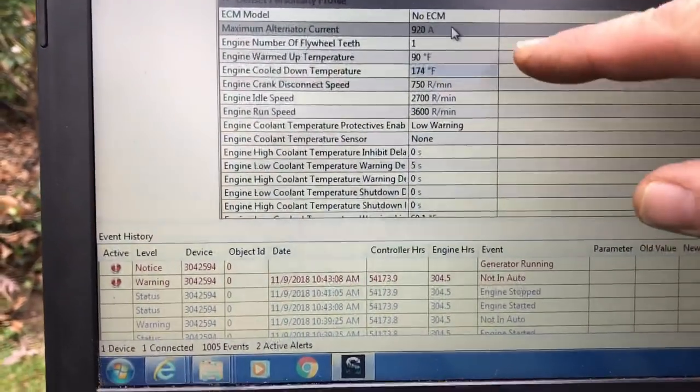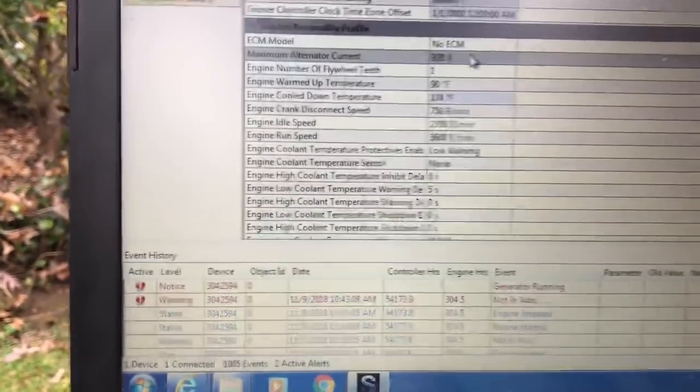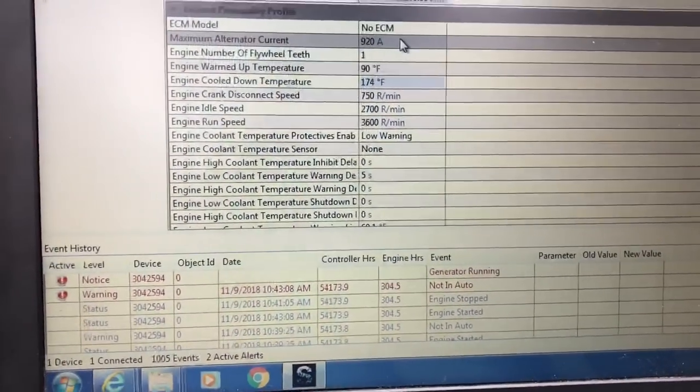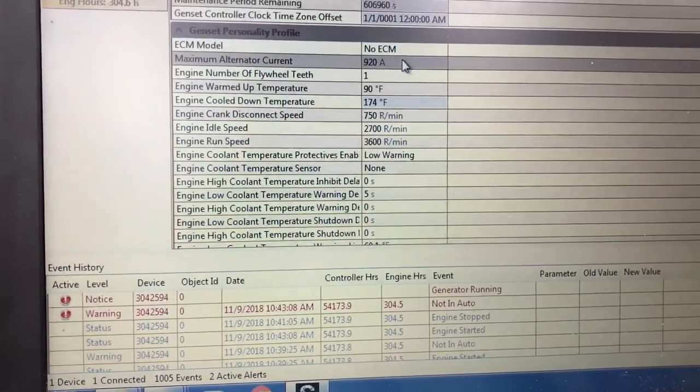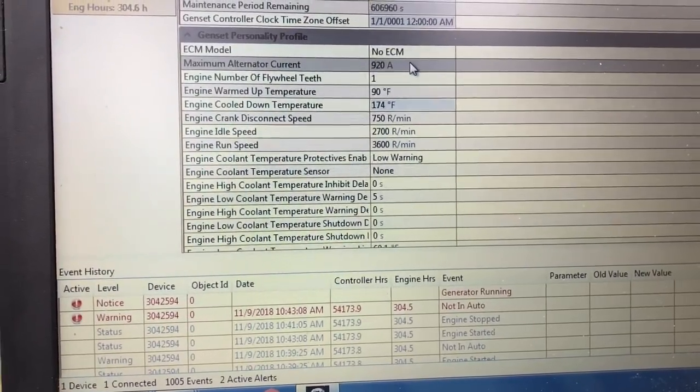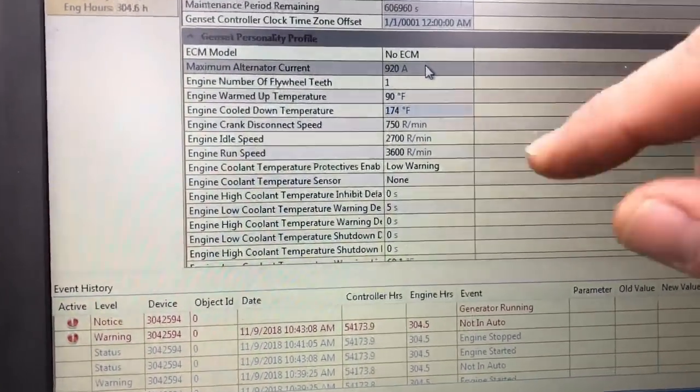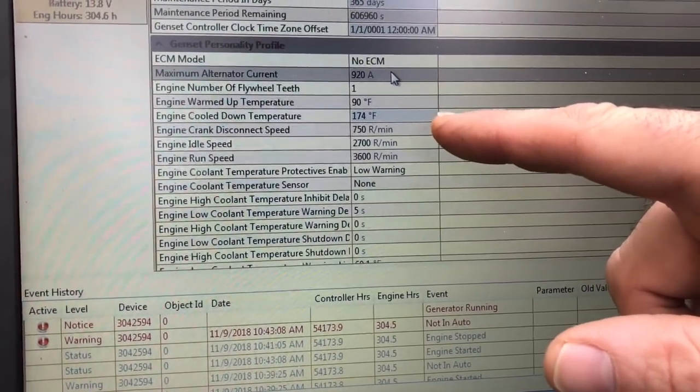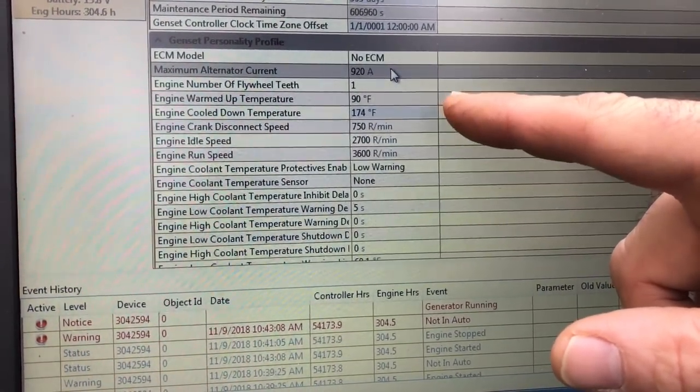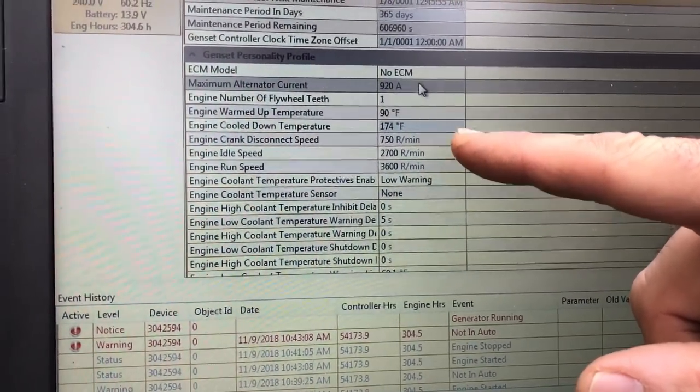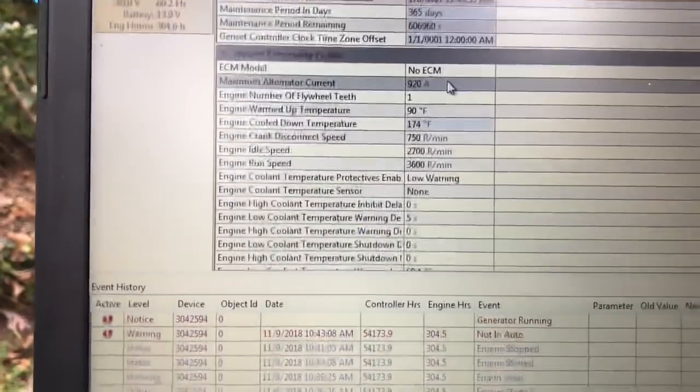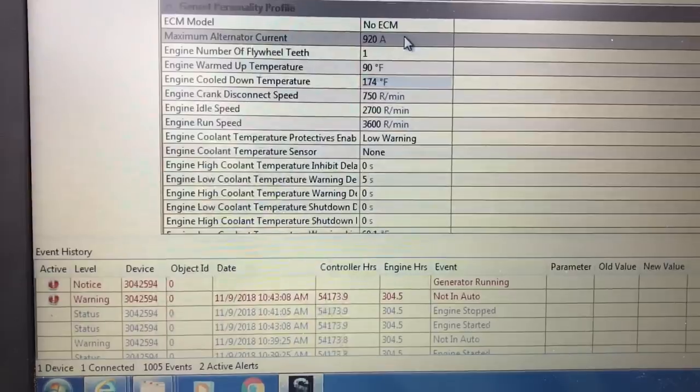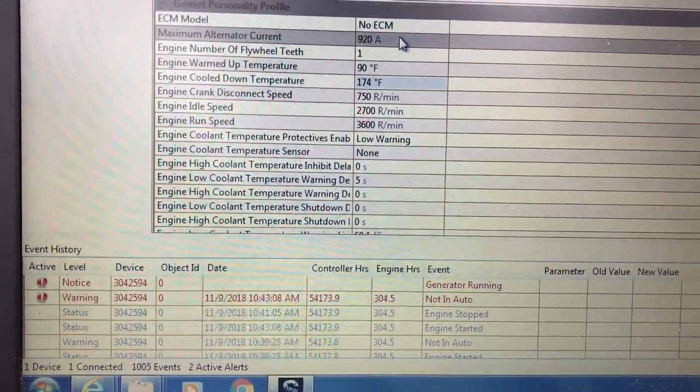...this generator is going to go into a cool-down. The last video I made, it was hunting within the cool-down, so that meant I got the generator over 174 degrees. And then it started hunting in the cool-down mode, and I was able to correct that just by changing an advanced speed gain. The engine crank disconnect speed is 750 RPMs. Now, the idle speed is 2700. I don't recommend doing a low-engine speed test, it sounds like it's stalling the whole time. The engine run speed, it's always looking for 3600.